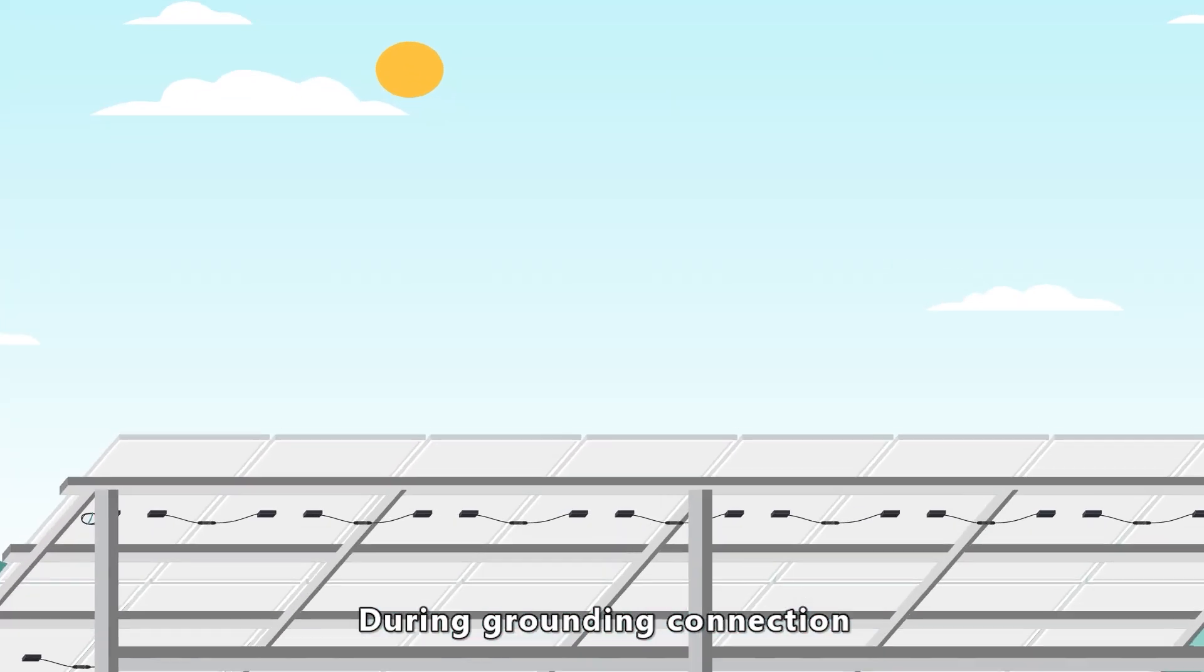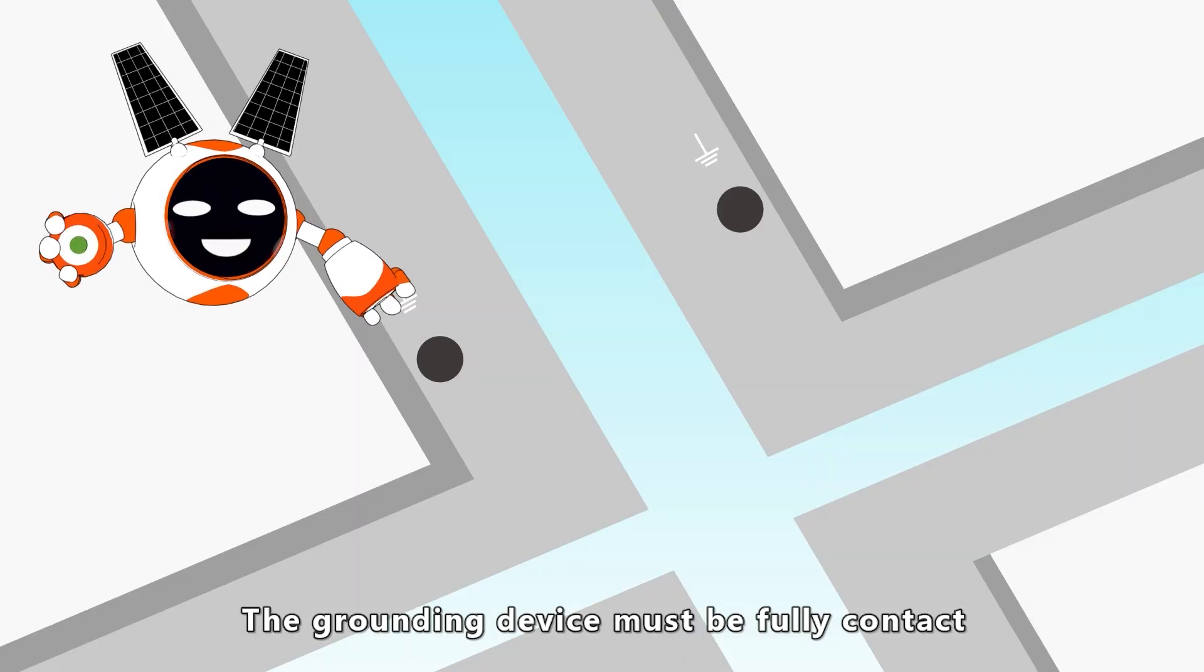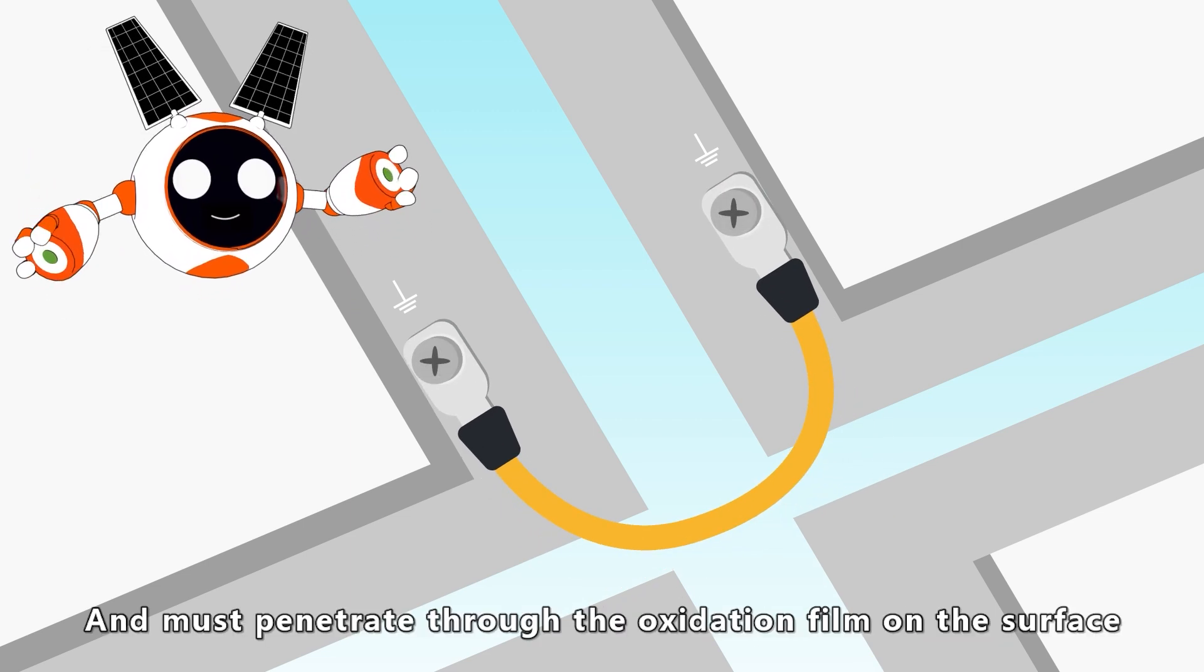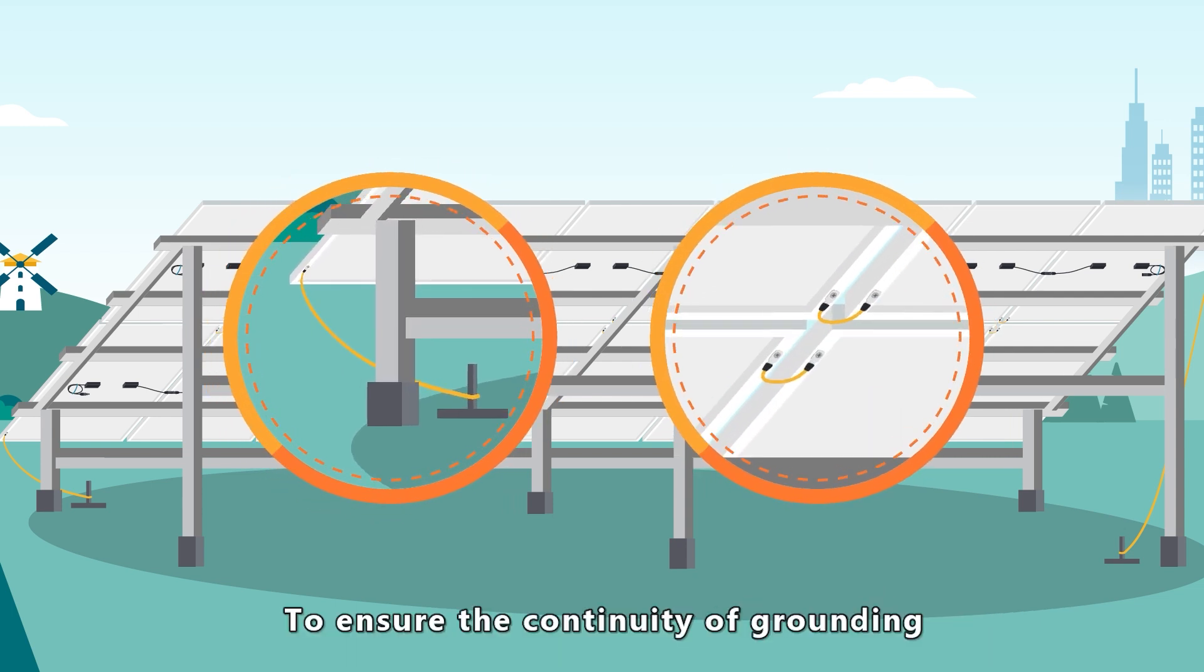During grounding connection, please use the grounding hole with grounding mark on the frame. For connecting, the grounding device must fully contact the internal aluminum alloy and must penetrate through the oxidation film on the surface to ensure the continuity of grounding.